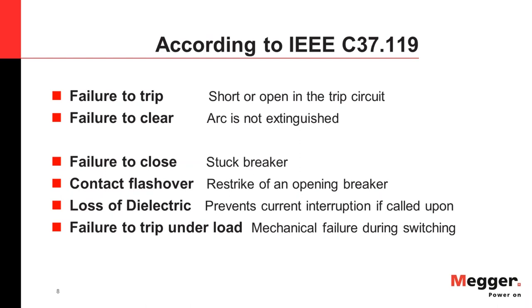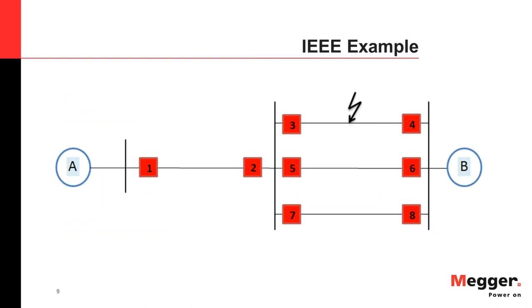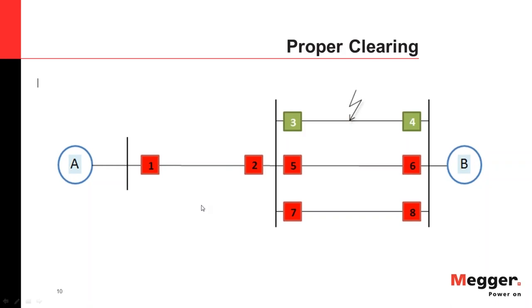Other conditions that can lead to Breaker Failure include: Failure to Close, which is a stuck breaker condition where it cannot close due to mechanical problems; Contact Flash Over, common when there is a re-strike of an opening breaker; Loss of Dielectric, where dielectric pressure falls below a certain level preventing current interruption; and Failure to Trip Under Load, where mechanical failure occurs during load switching rather than a fault condition.